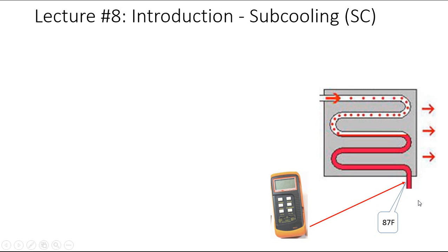The other thing too, as I mentioned before you ever get into doing diagnostics of subcooling or superheat for that matter, you want to make sure that your thermometer has been properly calibrated. And as I mentioned before, just get a styrofoam cup. You want to fill it about half full of water, half full of ice. The smaller the cubes, the better. And you want to let it sit for a few minutes. Drop your probe in there and make sure you're reading exactly 32 degrees Fahrenheit. Usually, as I mentioned, they have a calibration port, usually a little screw or a pot that you can change and calibrate your meter. I've seen many cases where technicians are taken off in the entirely wrong direction simply by not having the right calibration on their thermometers or their gauge set for that matter. So make sure you get that.